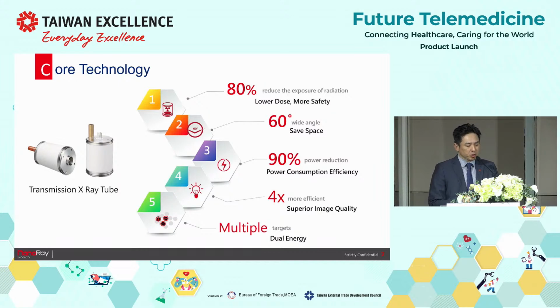Our X-ray tube luminous efficiency is 4 times greater than that of traditional X-ray. The image quality is far superior at the same energy output as traditional X-ray. So, at the same image quality as traditional X-ray, our transmission X-ray requires as much as 90% less energy consumption. We also developed the use of multi-composite targets, creating a dual energy spectrum that can be used in capturing images of both the bone and soft tissue with one exposure.